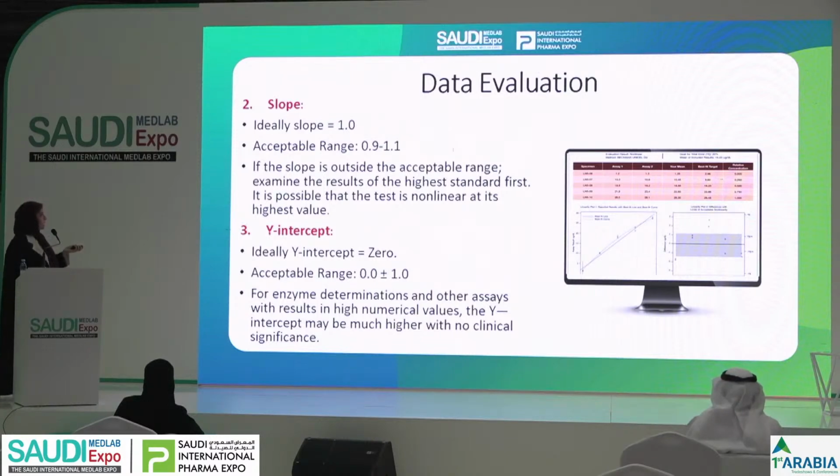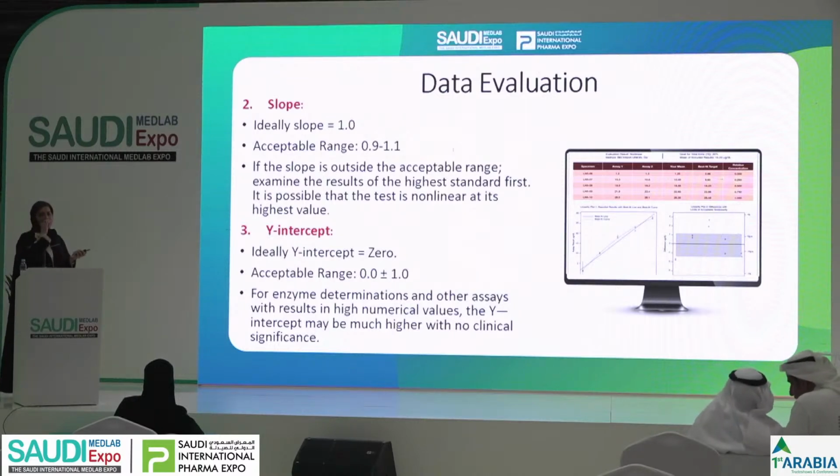And last thing is the y-intercept, it should be 0 or close to 0, and this is the range. And if it is out, the y-intercept may be much higher with no clinical significance. If it is, as I mentioned, the clinical scientists would accept it.